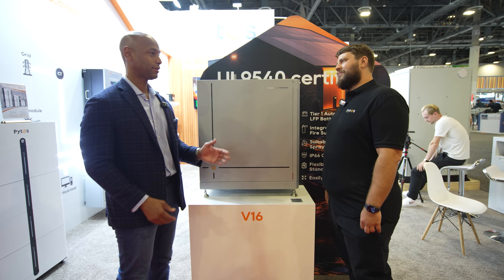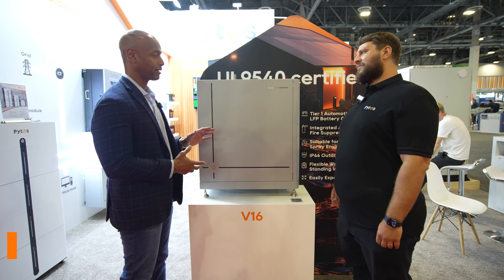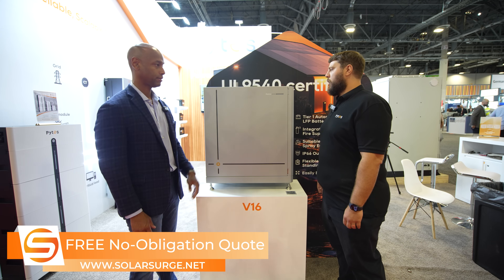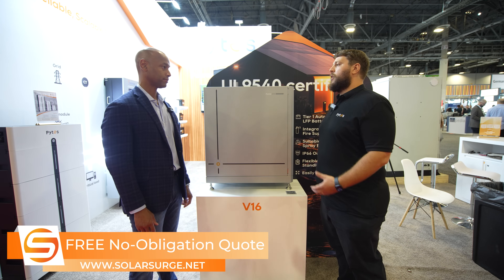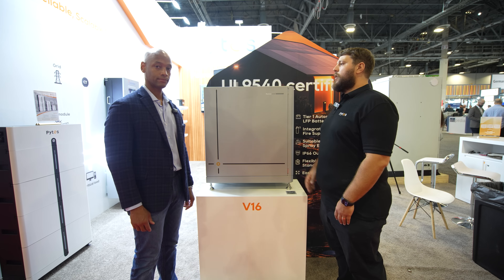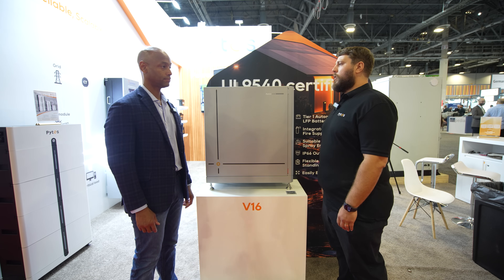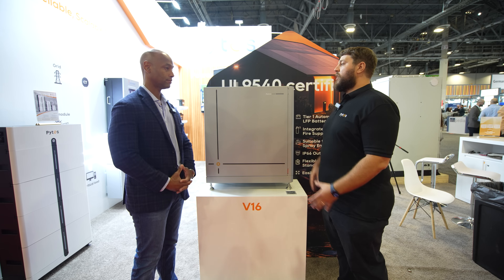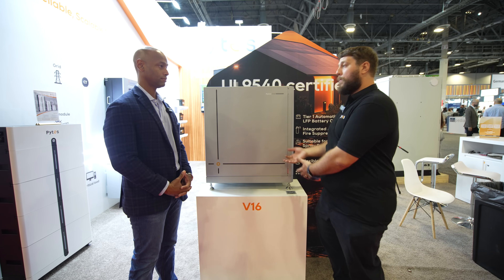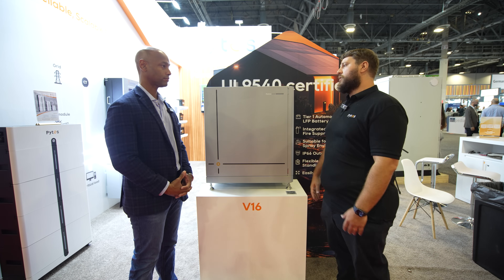I've seen a couple of other 16 kilowatt batteries introduced at RE Plus this year. Do you get more efficiency in terms of cost per kilowatt hour at the 16 kilowatt hour size versus the 10? Absolutely, that is where the trend is going. Because we use 314 amp hour cells, the cost on that compared to your typical 100 amp hour is a lot less price per kilowatt hour, so you're getting more bang for your buck when you jump up in cell size.